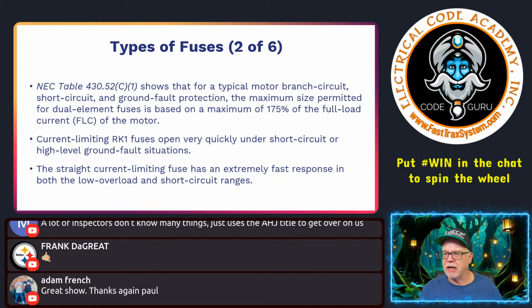Okay. Current limiting RK1 fuses open very quickly under short circuit and high level ground fault situations. When you hear somebody talk about a current limiting fuse, it's exactly what it sounds like. It is a specific value, and under a short circuit condition, this is what it's going to open at, and it is going to limit the amount of current.